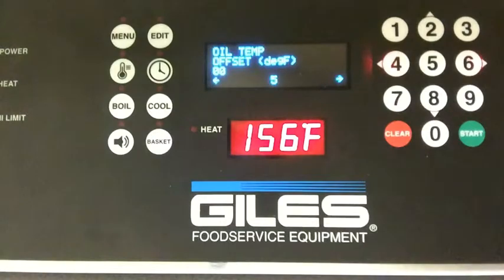The oil temperature offset is a calibration factor. If you found that a new controller and probe were not going together very well, and you were reading one temp with your probe and another one with the machine, you may want to set this. We don't recommend that you adjust it more than 10 to 15 degrees. Any more than that, as the temperature rises, that will expand, so it gets farther and farther away from your actual reading. So no more than 10 to 15 degrees maximum. In most cases, you'll never use it. It'll stay at 0.